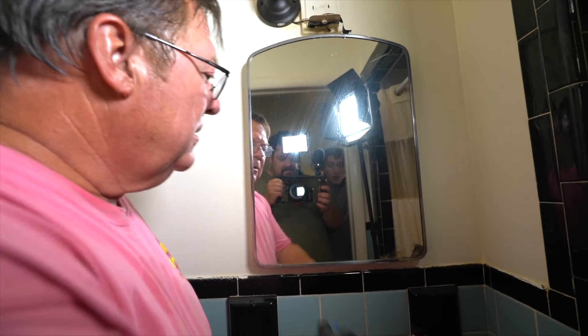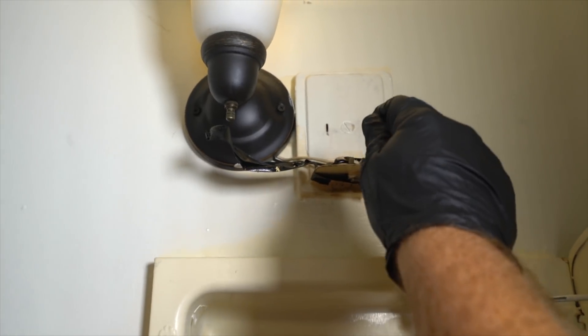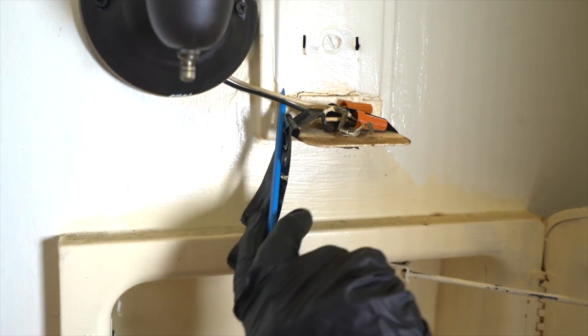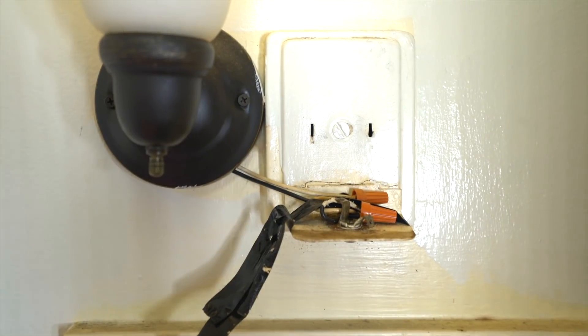Anything in the medicine cabinet? Empty. Oh my god, look at that electrical. The electrical is so shoddy. I think they had the old unit fastened to the wall, then just took wire nuts and attached whatever this light was. They took the wire and attached this — two wire connections but it's completely exposed and looks horrible. What you should have done is gone into the box, chiseled out here, run the wire in there, installed it, put some putty on, and hidden it. Every connection should be within a junction box — it can't be in the open like that.